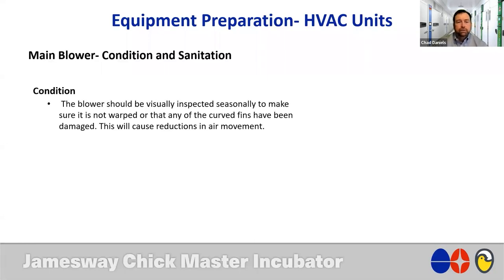We talk about main blower condition and sanitation. From a condition perspective, it's very good to make sure that you do a visual check on the blower and make sure that it's not warped or doesn't have any damaged fins, because either one of these occurrences can cause a reduction in air movement.